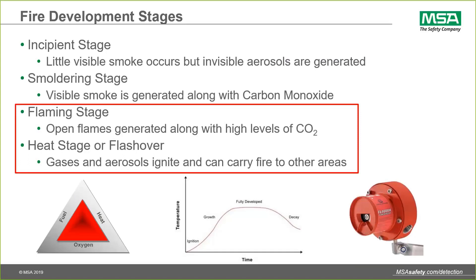Without a flame, you're not going to have the energy level required to create an alarm. I also wanted to show the curve of how a fire reaches the fully developed stage or equilibrium stage. This is important — not necessarily for gaseous fuels, but for some liquid fuels like kerosene and fuel oils that take a while to reach that fully engulfed stage, and that is important from the approval agency's perspective.